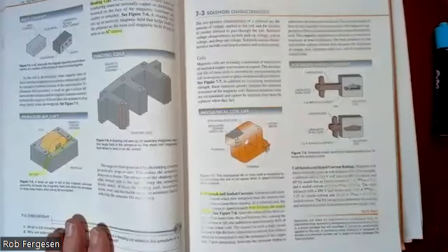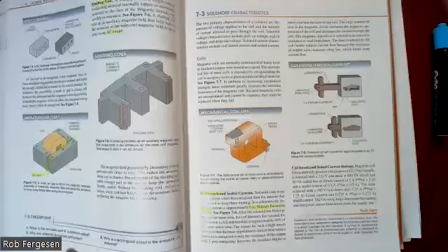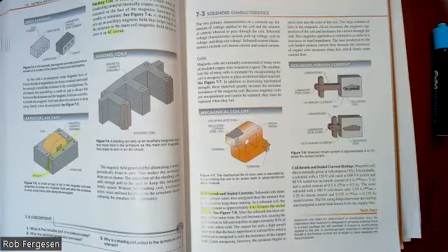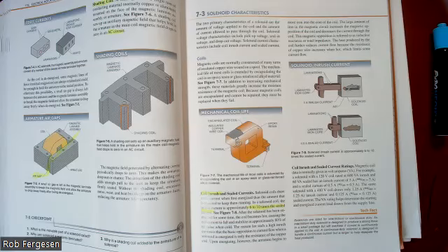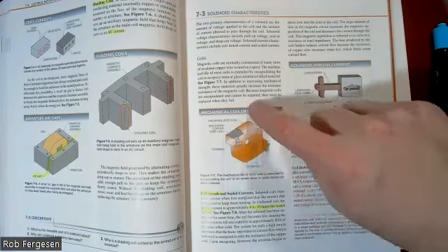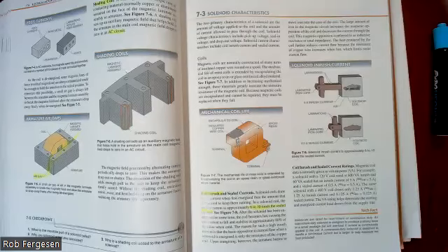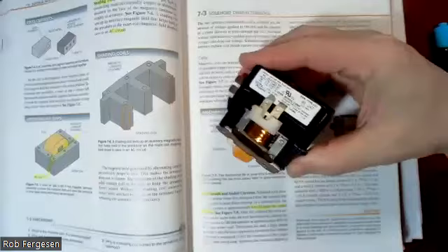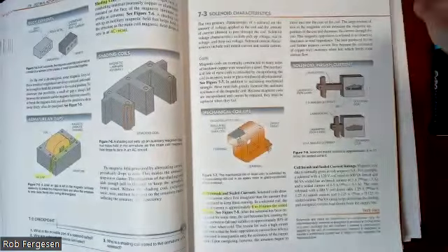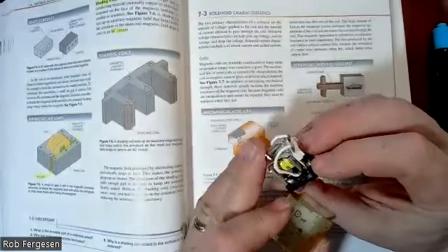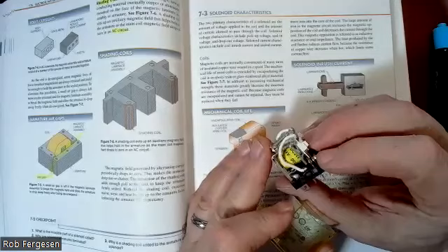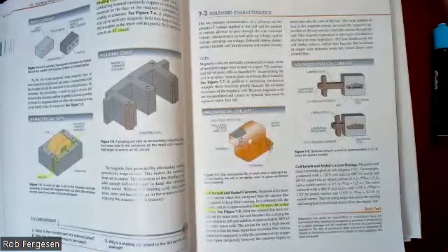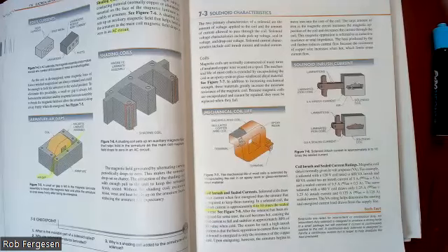Once we get to page 177, section 7-3, we talk about basic solenoid characteristics, how they're built, how they're encapsulated. You have a covering on the coils in many cases. In both the coils I show you, this covering is clear plastic. You can see it shiny in there. This coil right here has some sort of probably a nylon or PVC covering on it. And so you want to protect your coil for a long life, especially in industrial environments where you have a lot of grease or things that might be breaking down the copper.